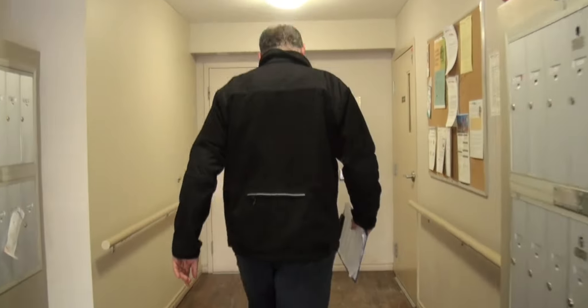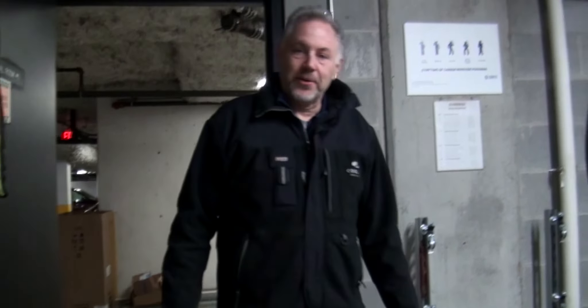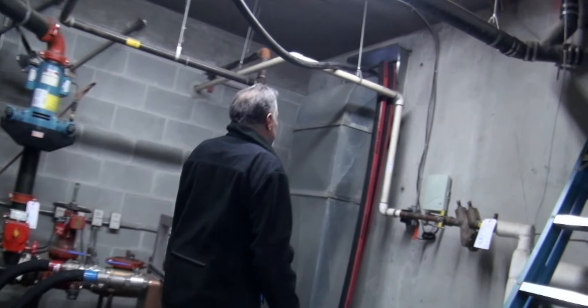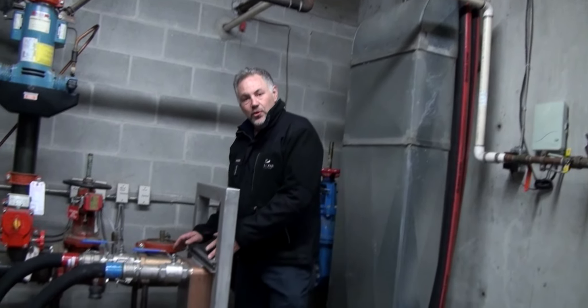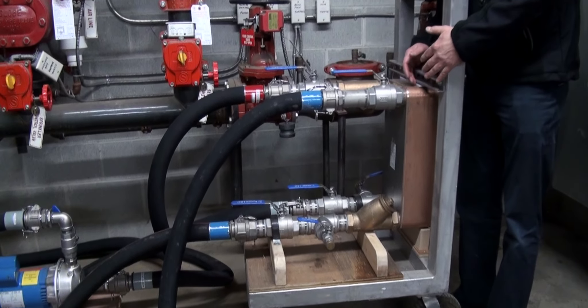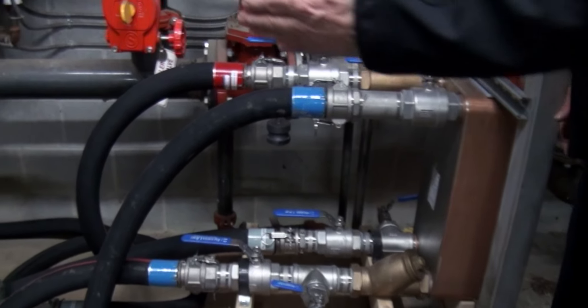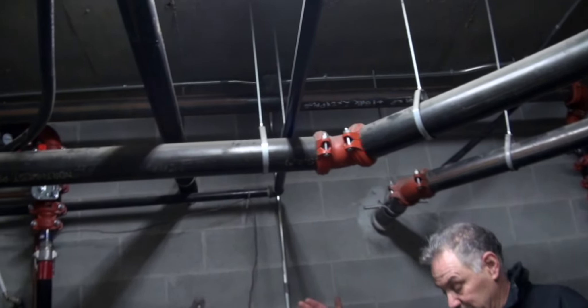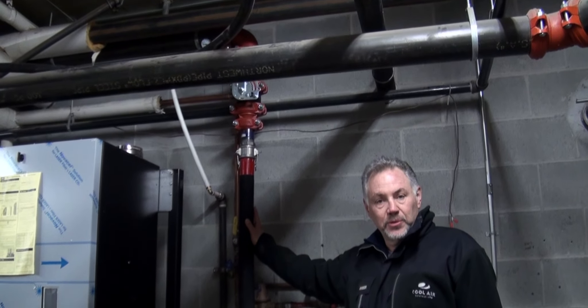This is the building's mechanical room. We enter through this louver and it comes down into our hydronic heat exchanger — or brazed plate heat exchanger. This is a transfer point; it's a sealed system that keeps our loop and the building loop separate. We use the pump to assist it into the building loop, where it enters and goes through all the radiators in all the suites to keep all the families warm. When it comes back, it enters back into this mechanical room through this pipe here.